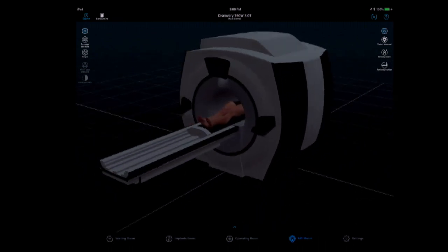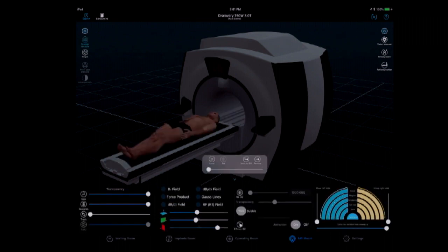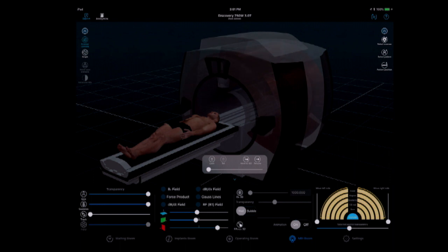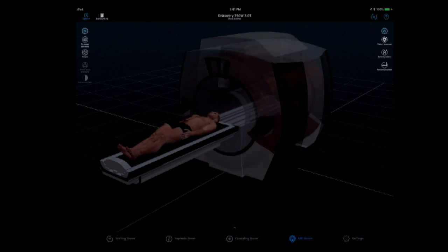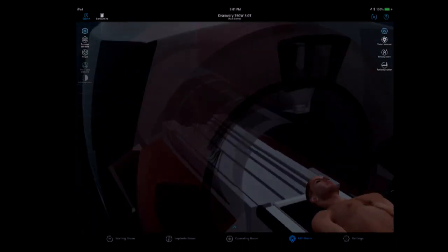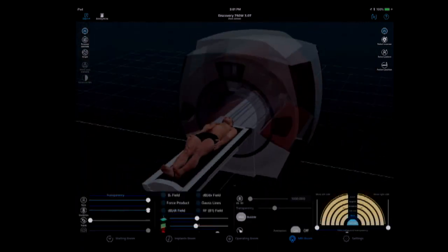Everybody see this? Again, it's a three-dimensional data set, so everything is modeled. That means that this is the exact, and I mean to the millimeter, dimensions of that make and that model of that system. But it also includes, let's bring the guy back out, the contents, which means that technically all the aspects of that device are there as well. The gradient coils are present inside. The RF transmitting coil is there inside. The magnet coil is there.